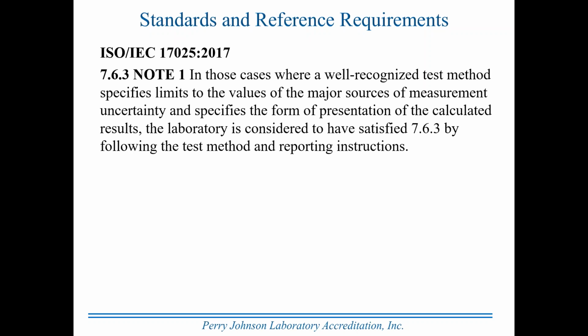So again, in tests, there are instances where the test method and procedure and equipment is well recognized, agreed to industry-wide, and used essentially throughout the world to perform the specific test of the specific material. If a laboratory follows the procedure, and uses appropriate equipment, trained technicians, and so forth, then typically they don't have to estimate uncertainty independent of that because it's built into the development of acceptance criteria.